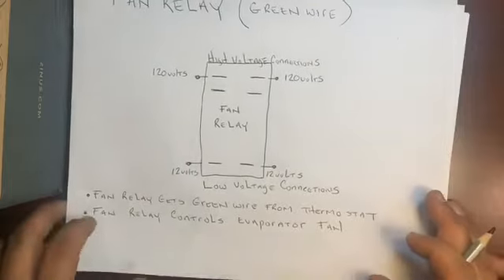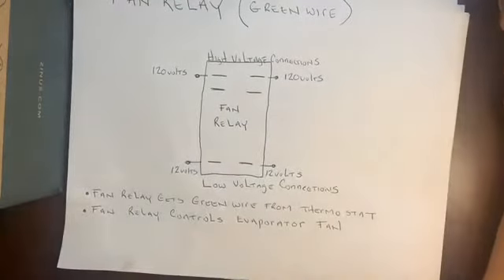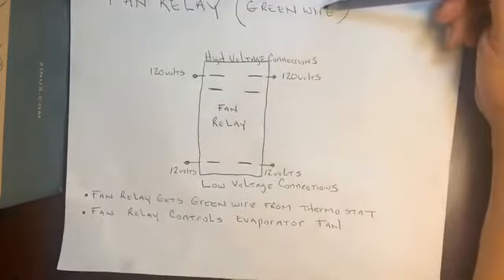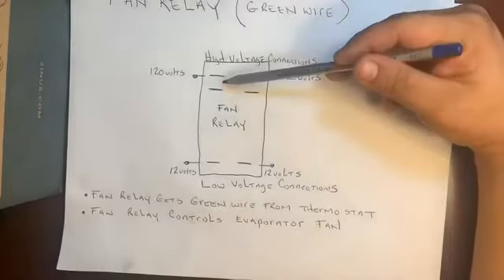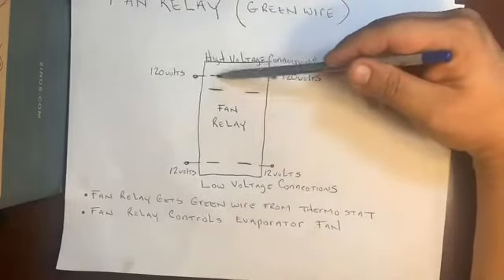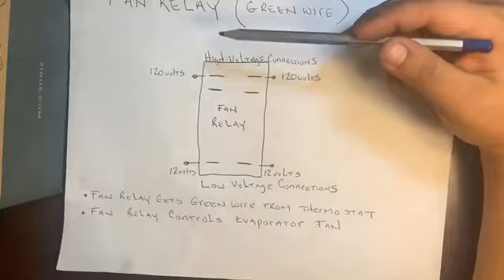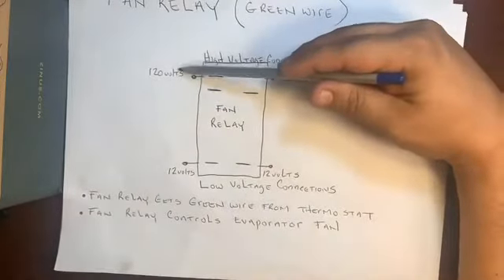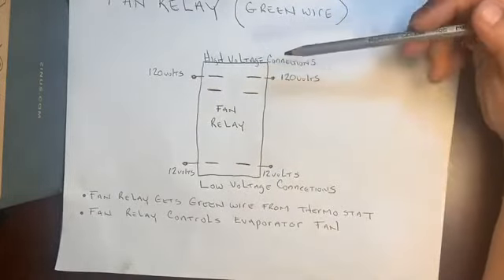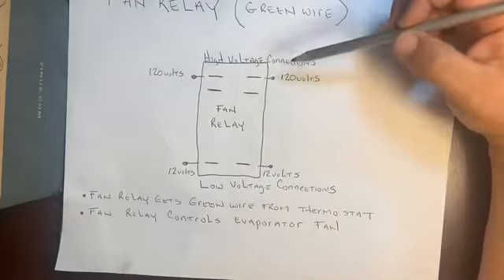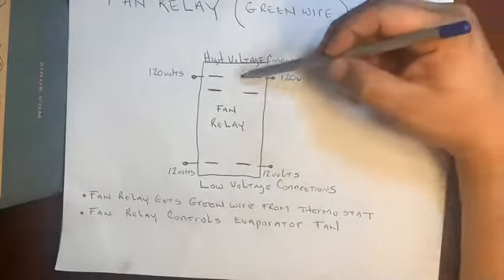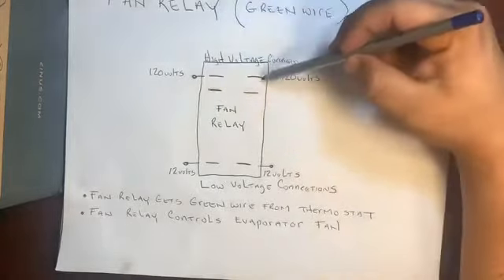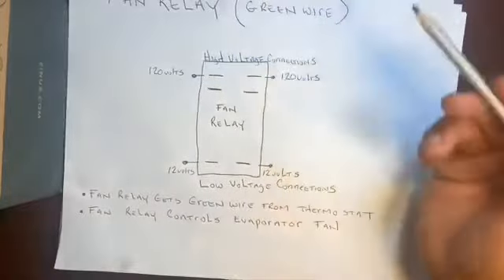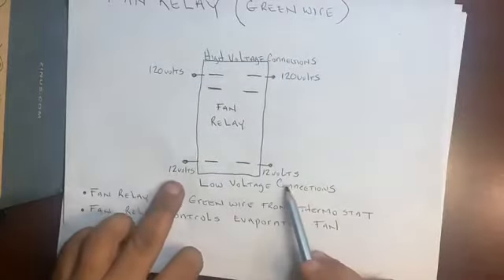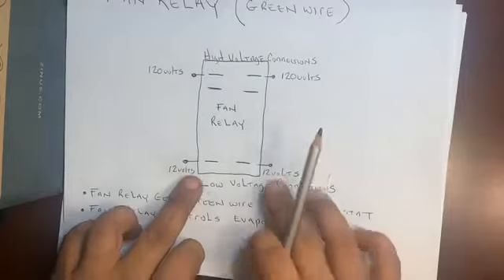This is inside of the air handler. This is what controls the indoor fan motor. Fan relay gets the green wire. The high voltage connections are at the top. When you look at a fan relay, you'll see 4 connections or sometimes 3. And this is where you know your 120 volts goes through. Your fan relay is just going to break one leg. So it's 120 that's going to jump over. When does it jump over? When we get 24 volts to the low voltage connections down here.